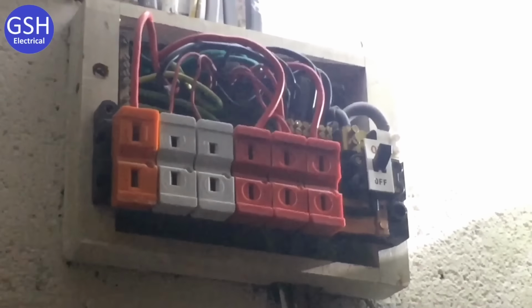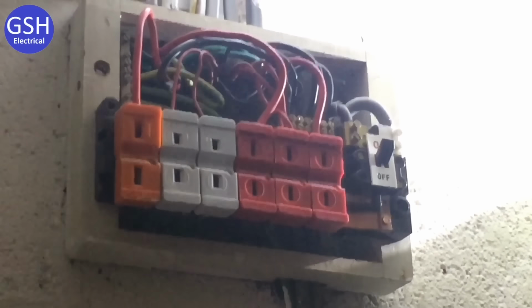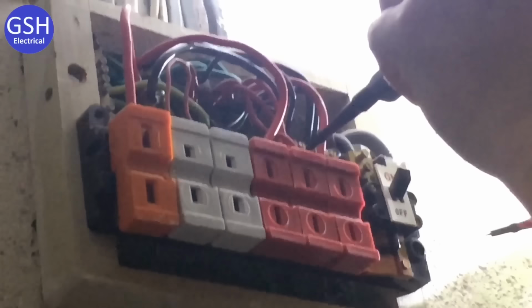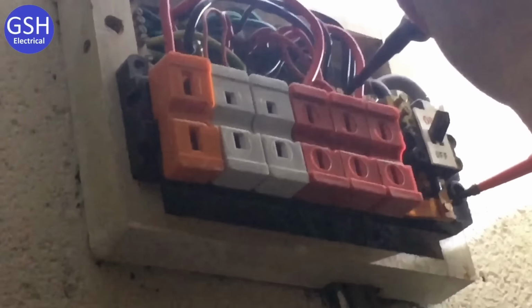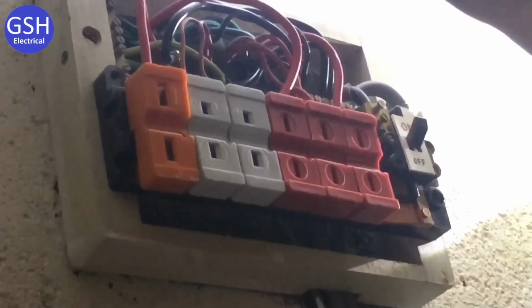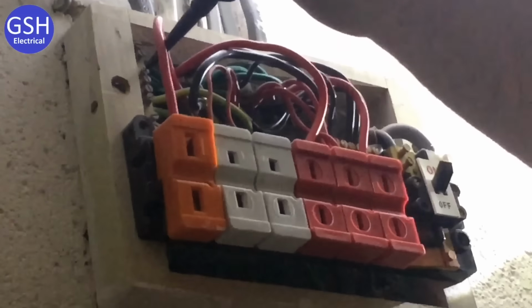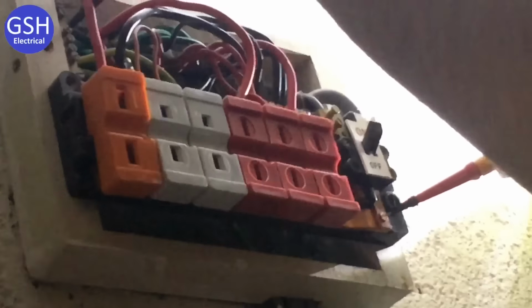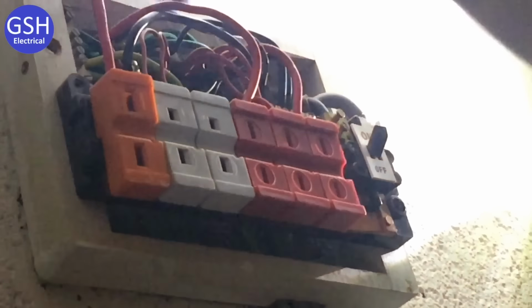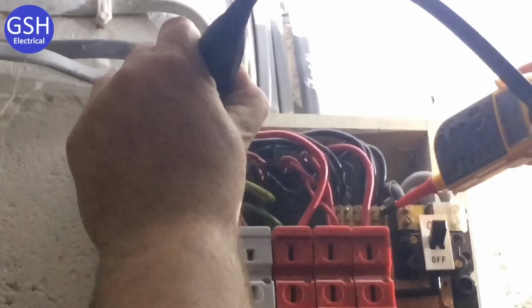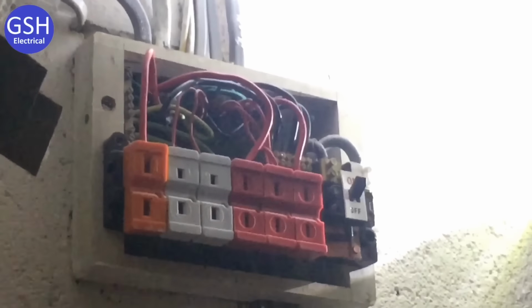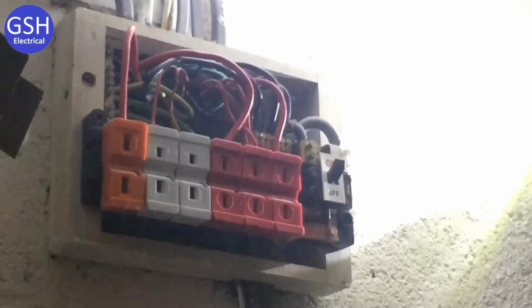I'm now just going to prove that the main switch has isolated the board. Okay, let's do that. So I'm probing onto the neutral bar and onto the line bar, and then I'm going to probe onto the earth bar and onto the line bar, and I'm going to probe onto the earth bar and the neutral bar. And what have you proved there? Now I've proved that all the circuits are dead in the board.